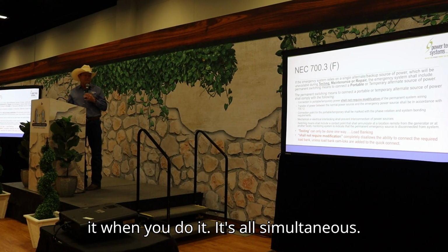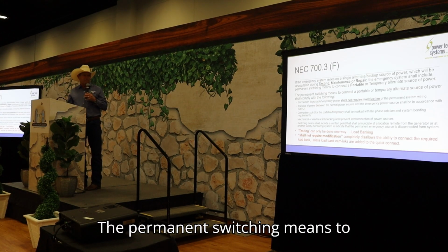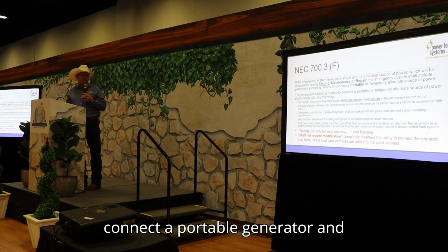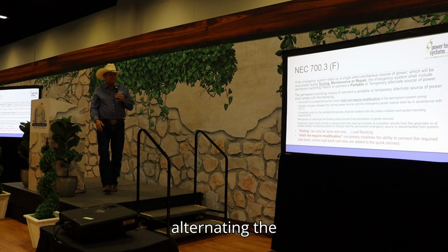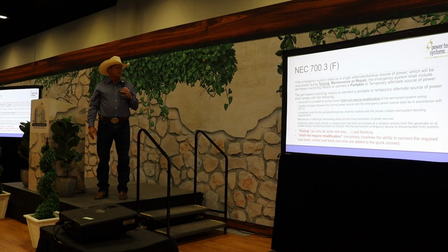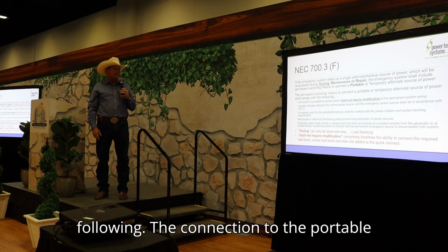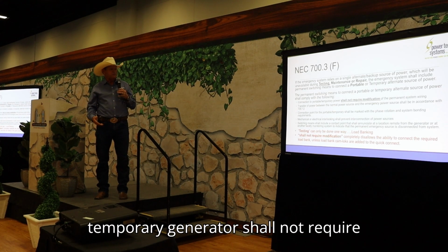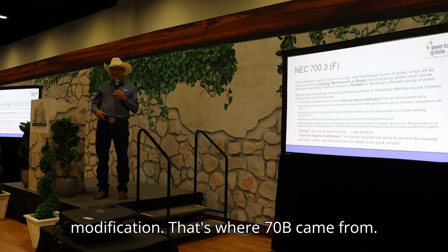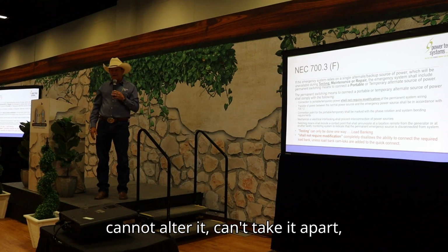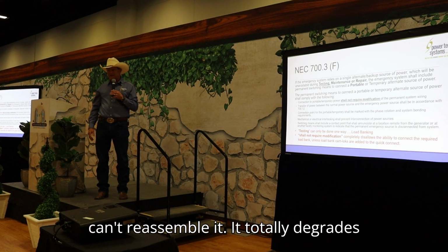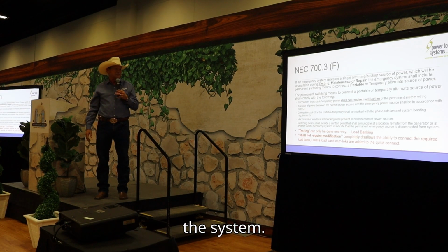It's all simultaneous. The permanent switching means to connect a portable generator as the alternate source of power shall comply with the following: the connection of the portable or temporary generator shall not require modification. That's where 70B came from. You cannot alter it, can't take it apart, can't reassemble it. It totally degrades the system.